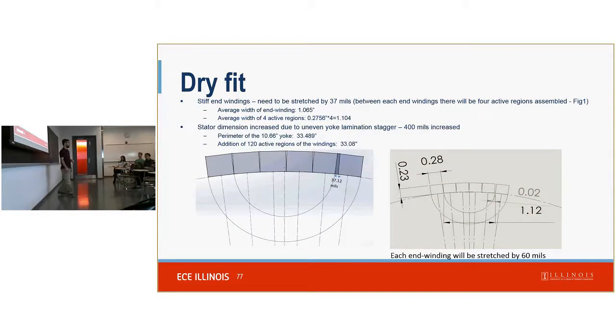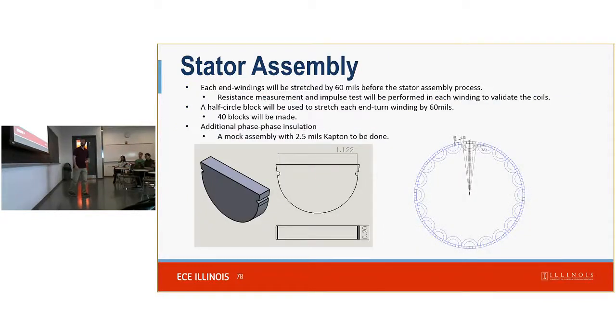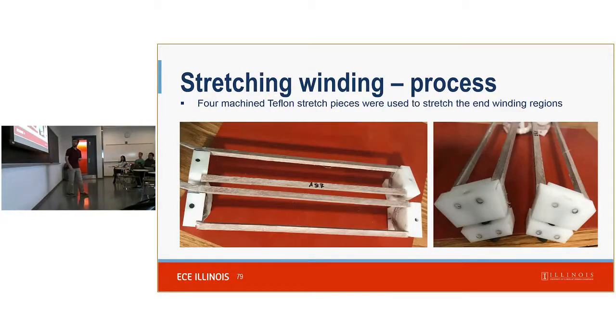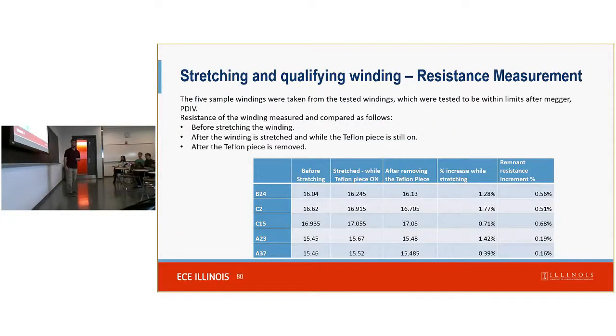And so in order to fix that, we realized that the angle between, or the space between the two sides of each coil was slightly too close together. And so they needed to be stretched apart slightly. And so a set of plastic or Teflon pieces was then used to stretch out those pieces. And here we can see the pieces applied that are doing the stretching and the process of that. And it's a little bit concerning when you have your resin that makes it very stiff, and if you stretch that, there could be risk of damaging the insulation within the stator.